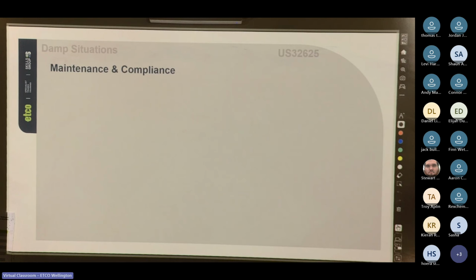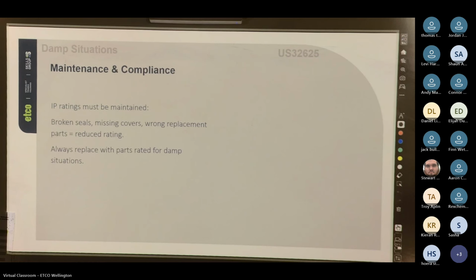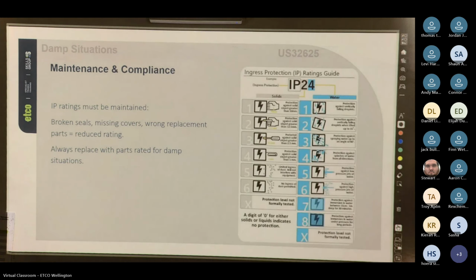Cool, so maintenance and compliance. IP ratings must be maintained. Broken seals, missing covers, and wrong replacement parts equals reduced rating. Always replace with parts rated for the damp situation. So an outdoor socket with a cracked gasket is no longer IP44.